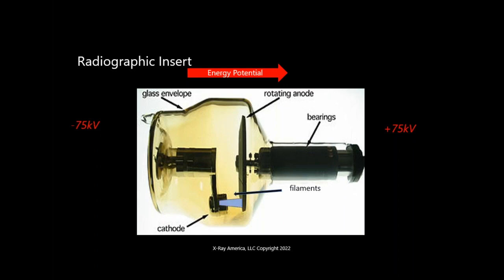So the filaments put a little power, low voltage, to this cathode head, and the filaments bleed off some electrons and create an electron beam. Because you have this tremendous energy potential, there's a tremendous amount of force when these electrons hit that rotating anode. What comes out is an X-ray beam, but also 99.7% heat. So there are a number of challenges. One is the bearings and lubrication of the bearings. That's number one: good quality bearings with very good lubrication. You need a very good vacuum in here so that beam comes out, and you need to manage your heat.